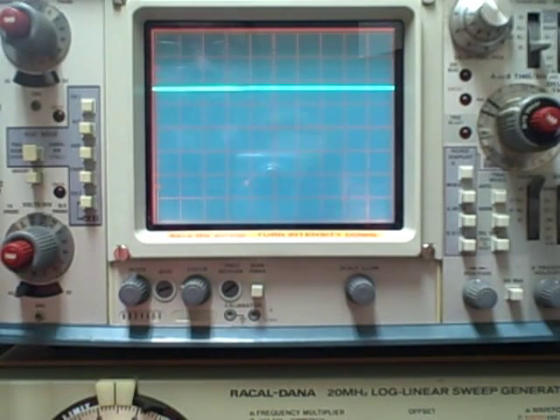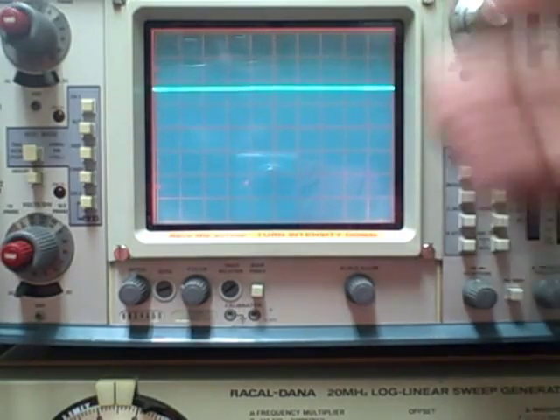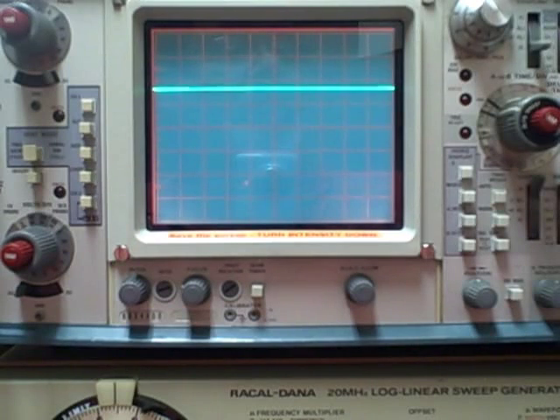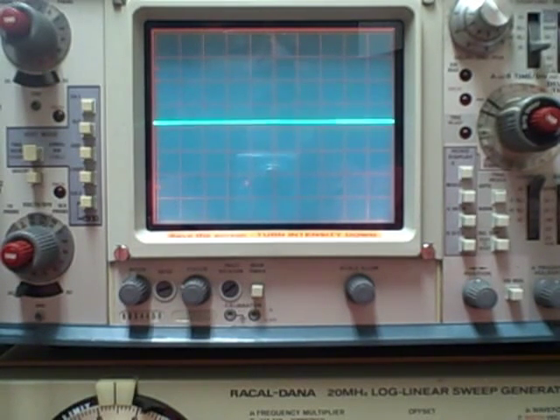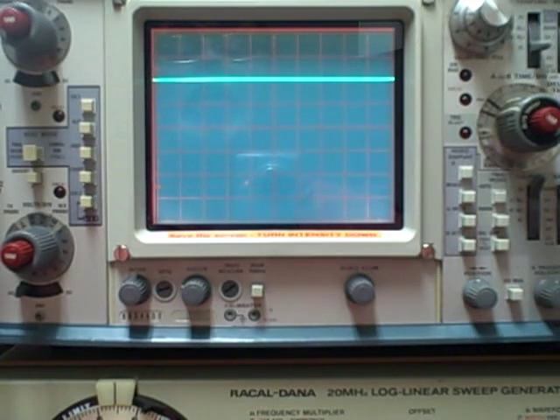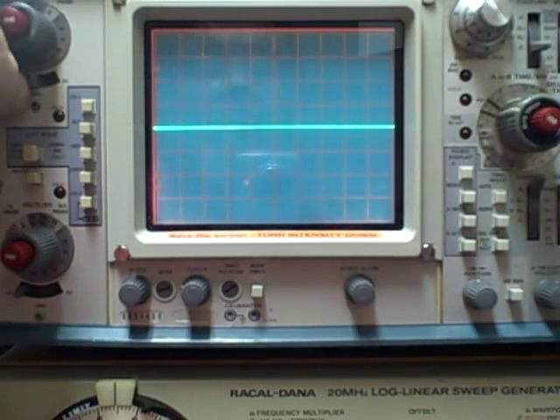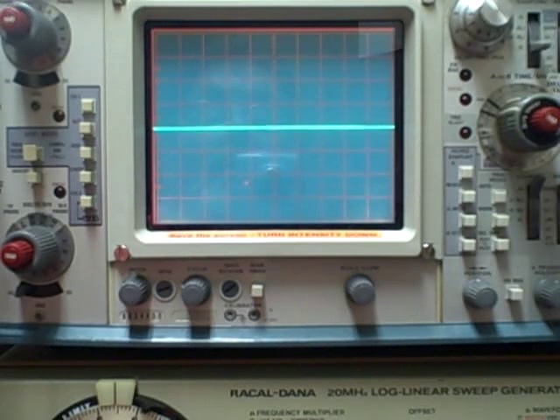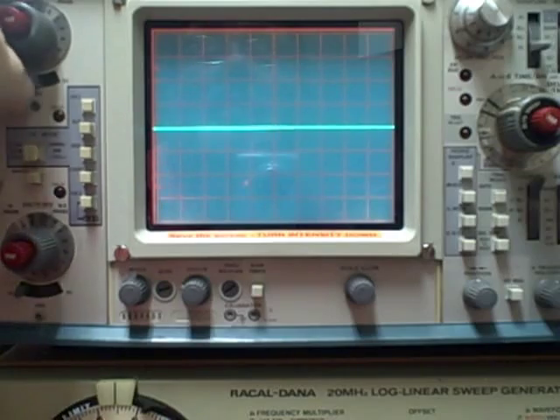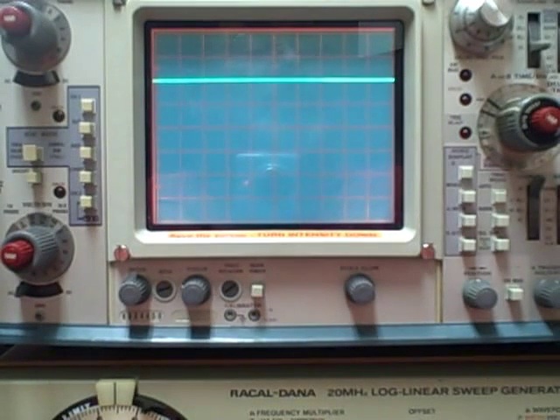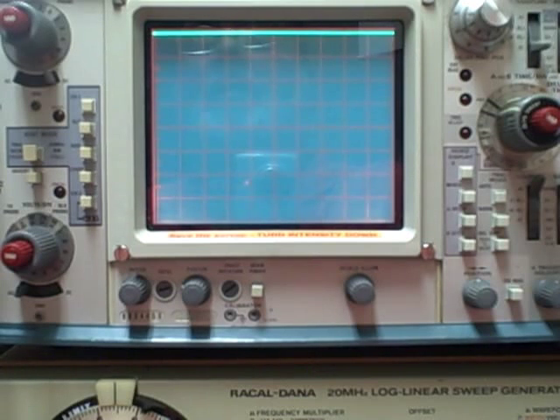At 50 millivolts per division, I'd have to be at 100 millivolts to be 2 divisions up. I'm slightly less than that because I have 80 coming in right now. So let's go to 100. Alright, 100 millivolts, and we are right on the line. Checking our scale. Right on the line. Perfect. Alright, so let's go to 0.2 volts. And we are at 50 millivolts per division. We're up 4 divisions. That's 0.2 volts. Alright, so we change our scale again.